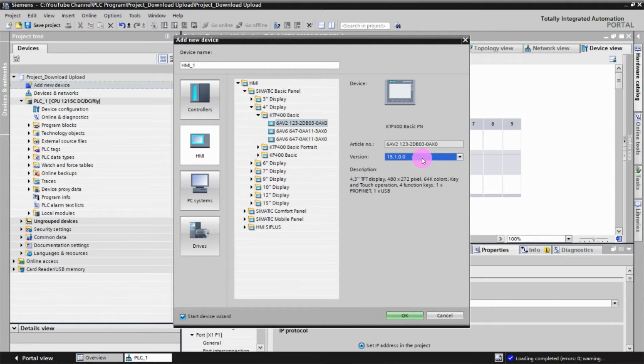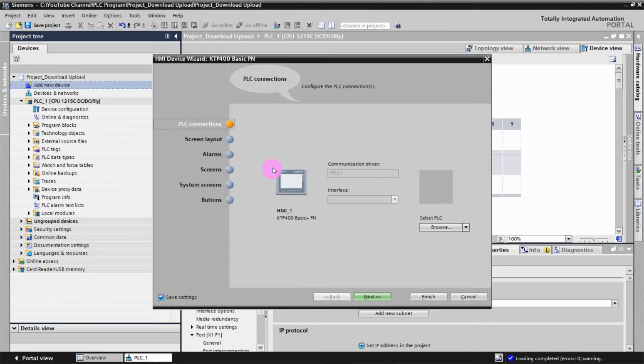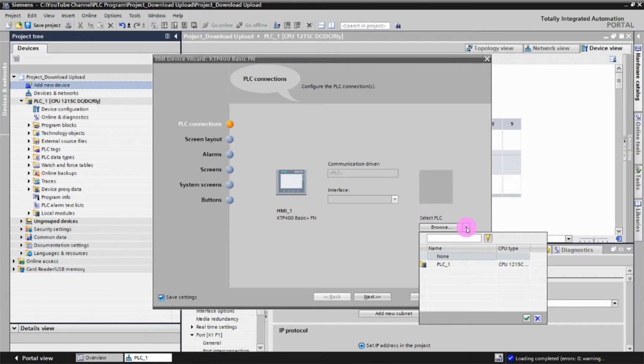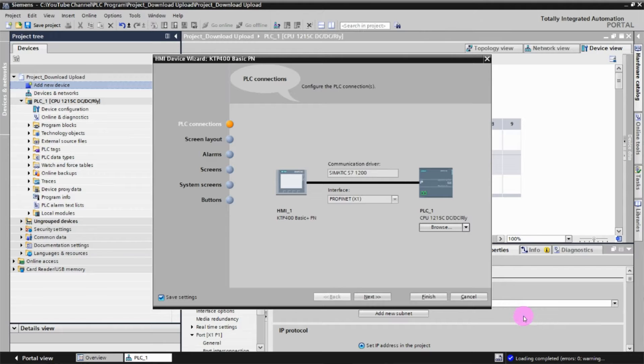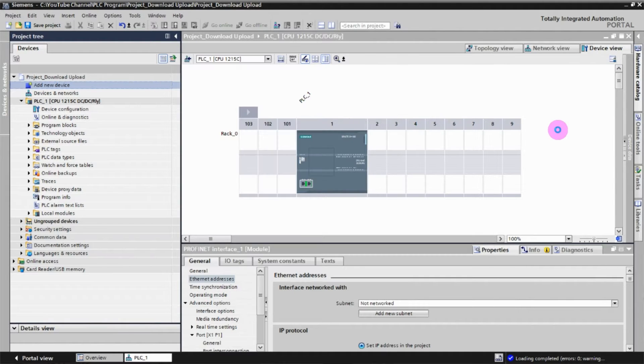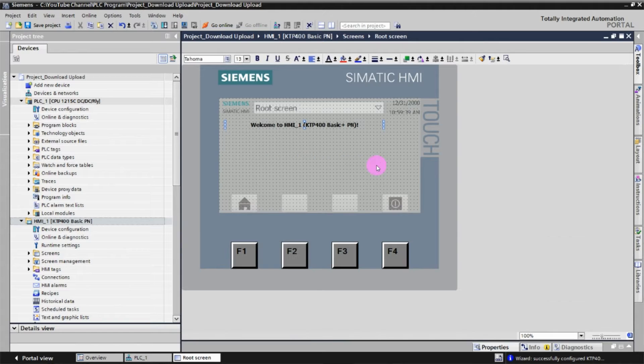I have selected the version matching my HMI, so now we click OK. This HMI device wizard asks you to set up communication to the PLC. Select your PLC — since there is already a PLC in this project, click on the PLC, click OK, then click Finish. This is how we add the HMI to the project.